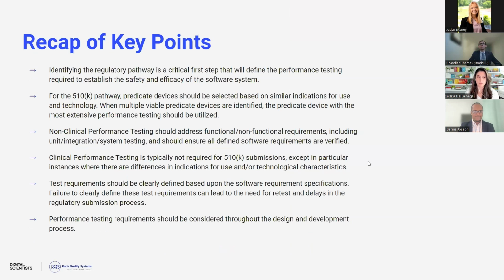So for a quick recap of our key points, identifying that regulatory pathway is definitely a critical first step that will eventually define your performance testing requirements, as well as establishing the safety and efficacy of the software system. Without that regulatory pathway, it's almost like you're running in the dark. You want to make sure that you turn the lights on and understand what you're going to have to demonstrate to FDA to be able to bring that device to market.